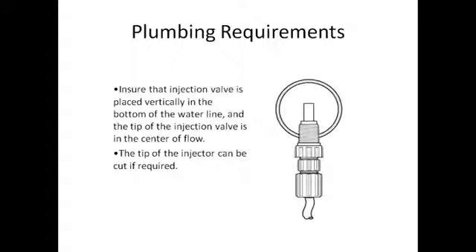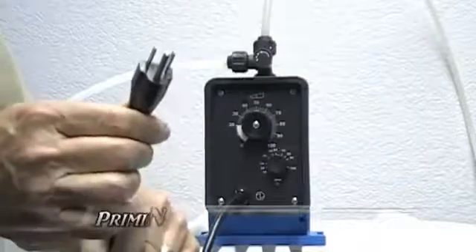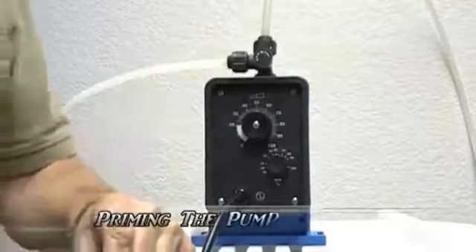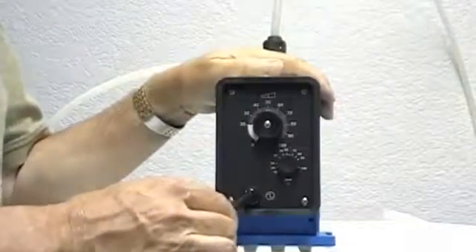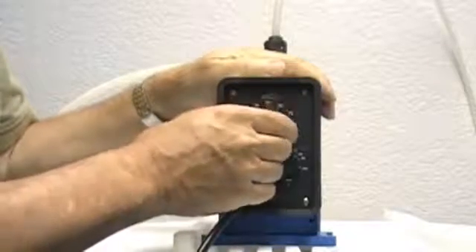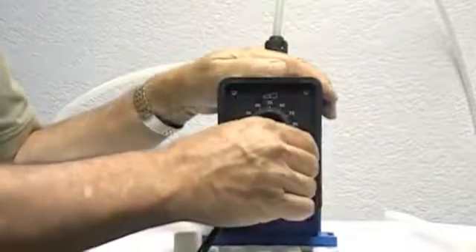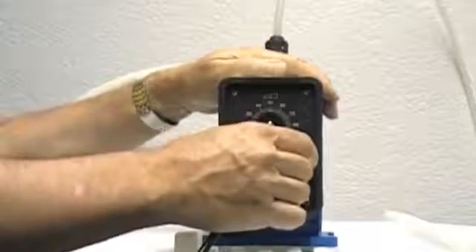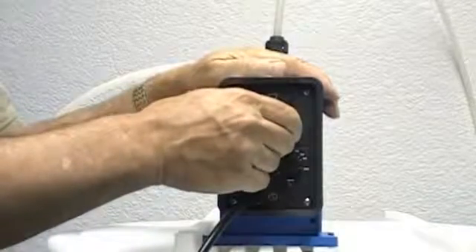In order to prime your pump, plug the cord into an appropriate receptacle. Please use a surge protector for the power supply of the cord. Be sure that the stroke length is adjusted to 100% and that the stroke rate is adjusted to 100%. Never adjust the stroke length while the pump is not running.